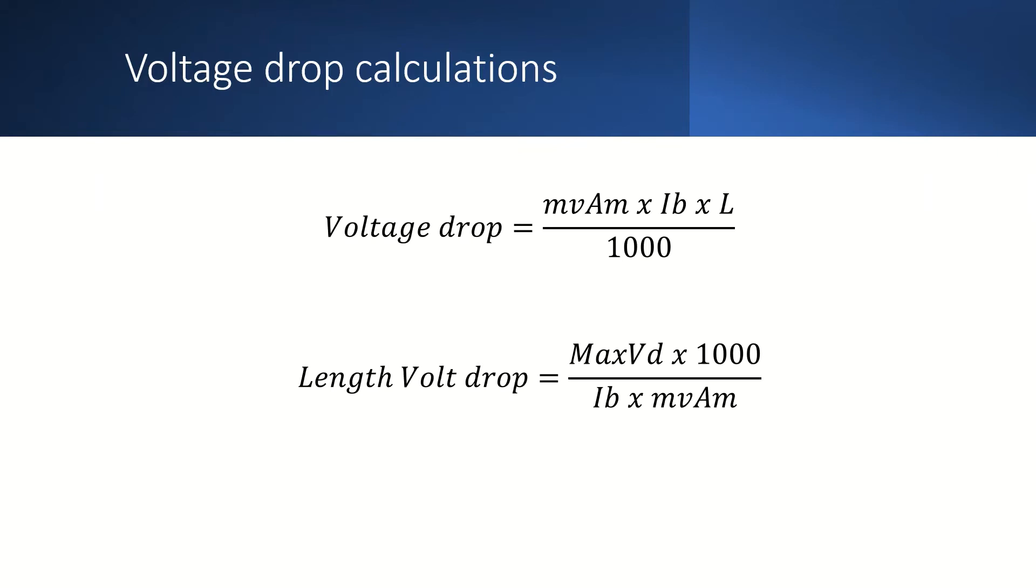So if we take the maximum volt drop for the final circuit either 6.9 volts or 11.5 volts for a single phase circuit and multiply by 1000.